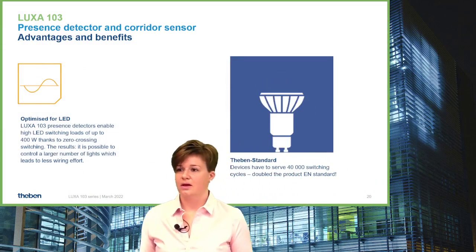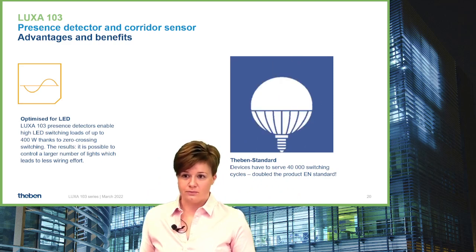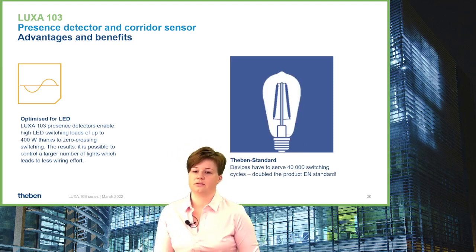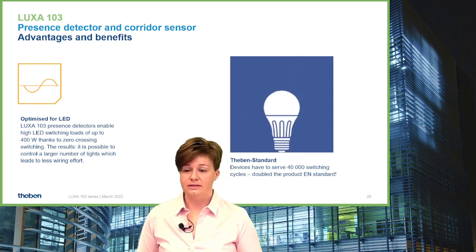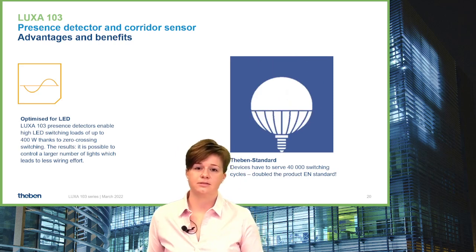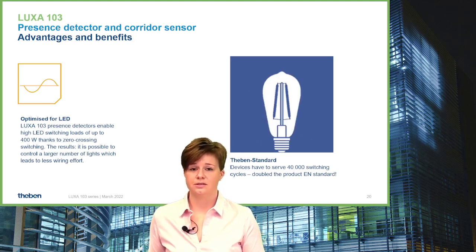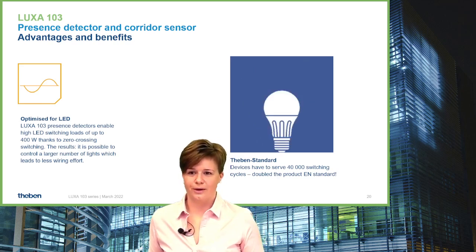Regarding LED switching capacity: 400W for LED is very promising. The product standard requires surviving 20,000 cycles with 400W LED, but this is not sufficient for Theben's quality understanding. Our internal Theben standard requires double the switching cycles compared to the product standard — meaning the LUXA 103 family can do 40,000 switching cycles with 400W LED, giving you important product reliability.